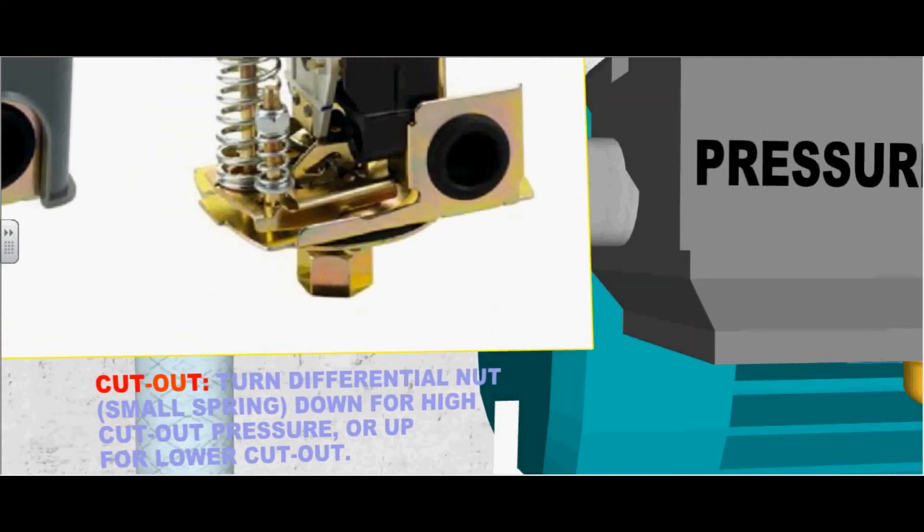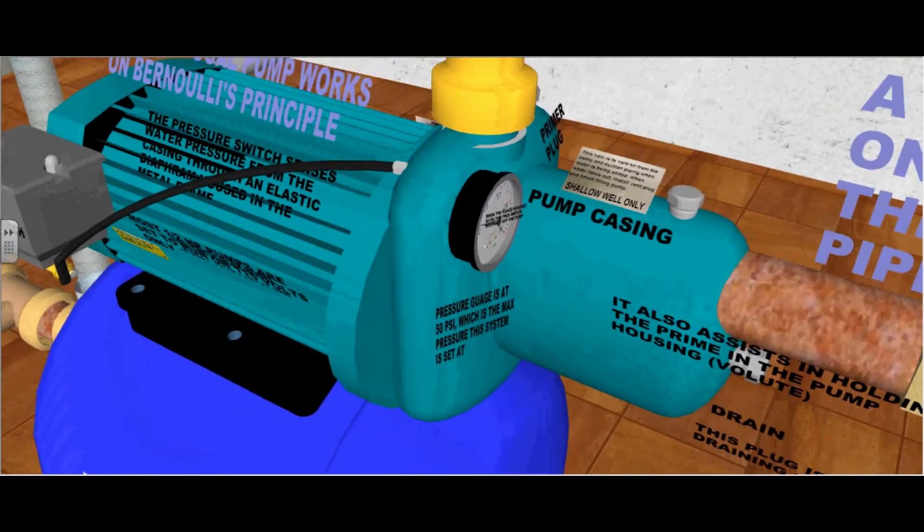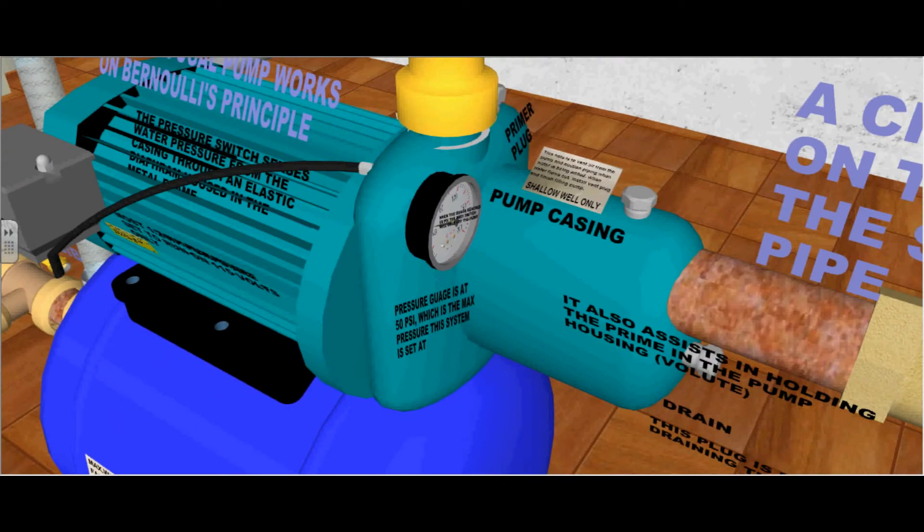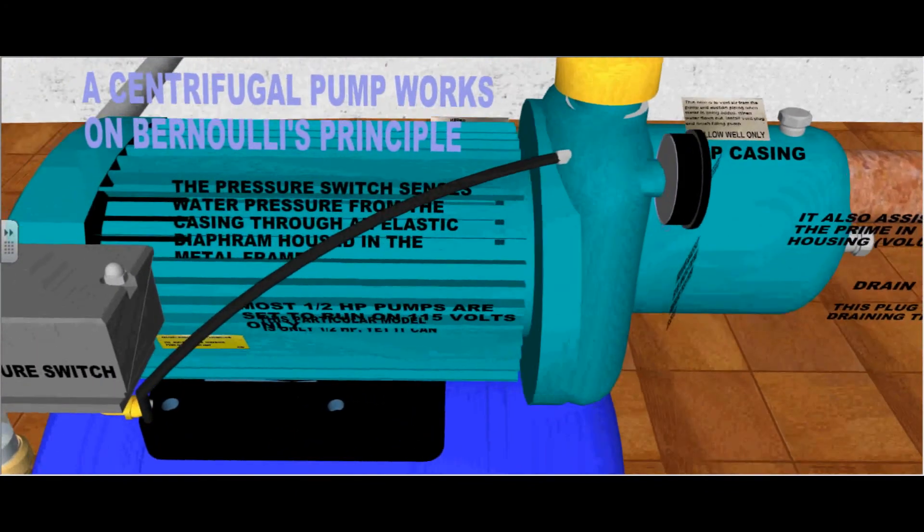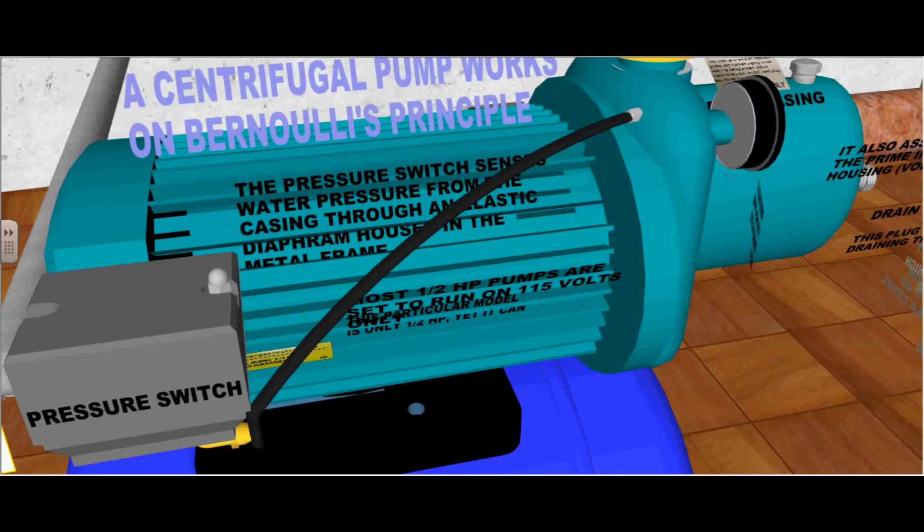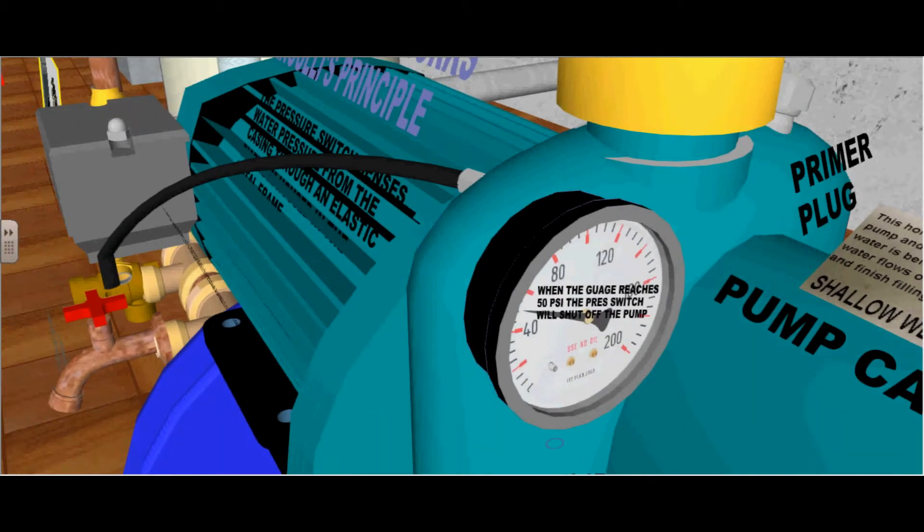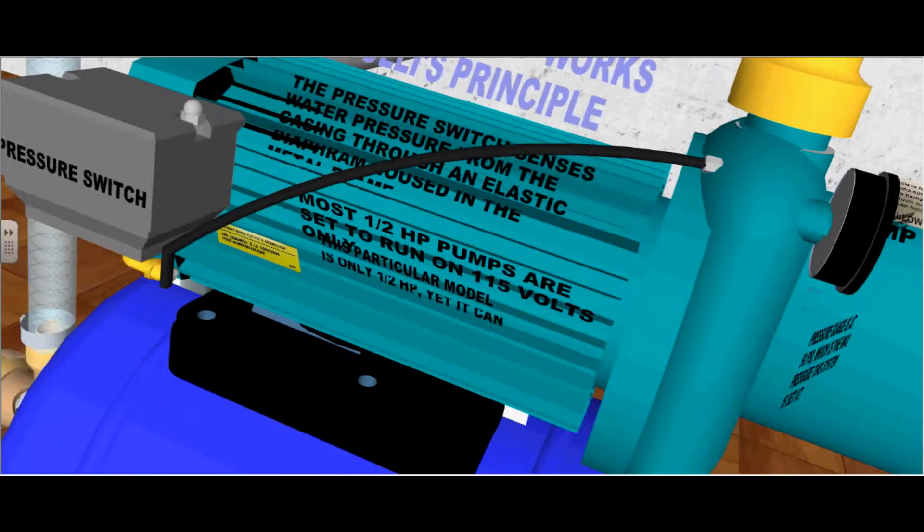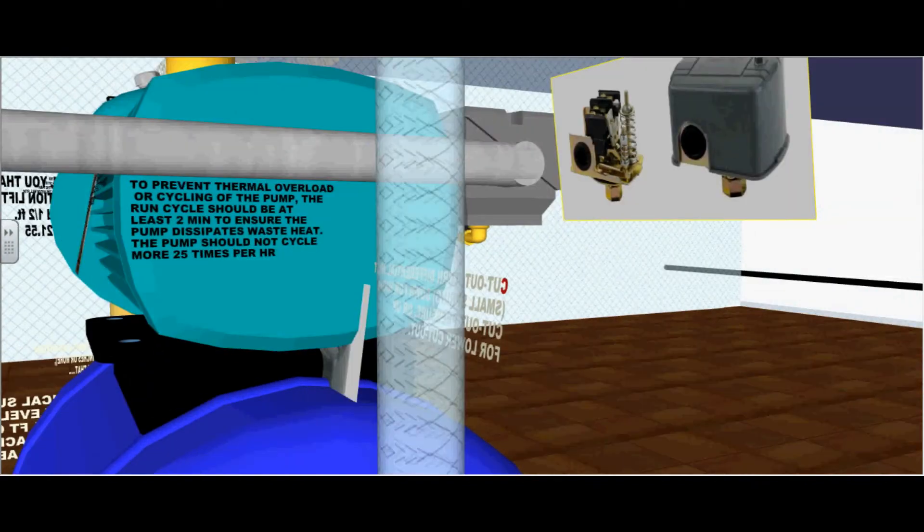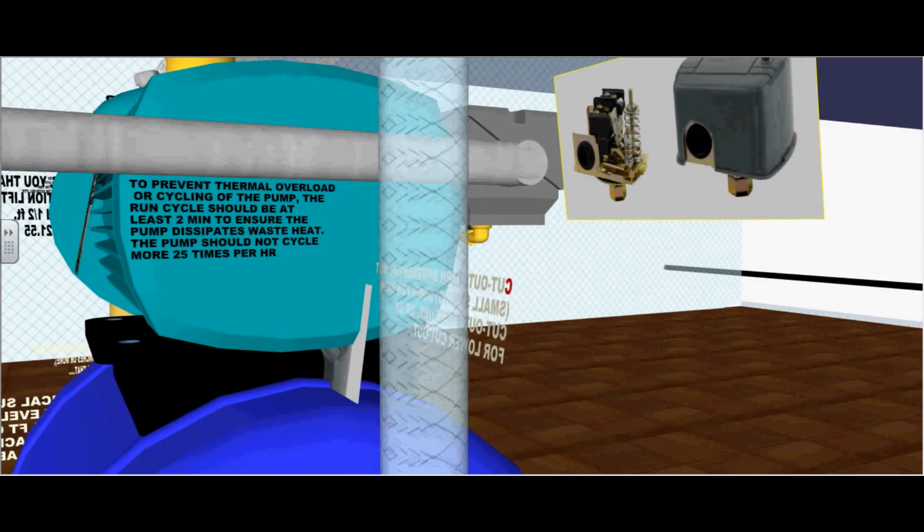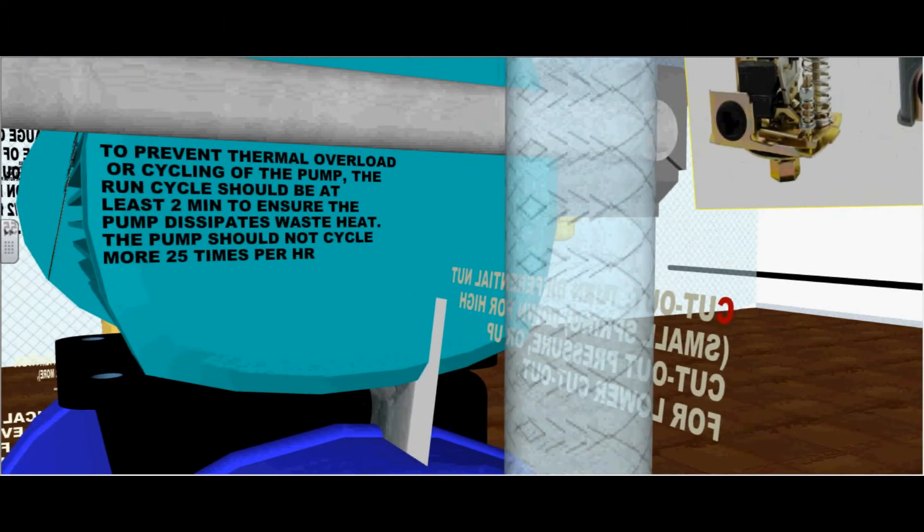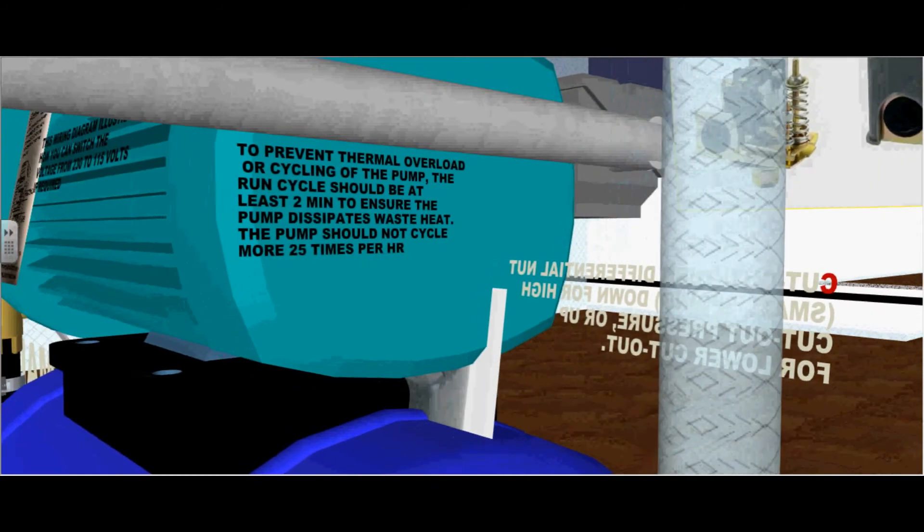This is how you adjust the pressure ranges of the pump. This pressure switch senses water pressure from the casing through an elastic diaphragm housed in the metal frame. When the gauge reaches 50 psi, the pressure switch should shut the pump off. To prevent thermal overload or cycling of the pump, the run cycle should be at least 2 minutes to ensure the pump dissipates the waste heat. The pump should not cycle more than 25 times per hour.